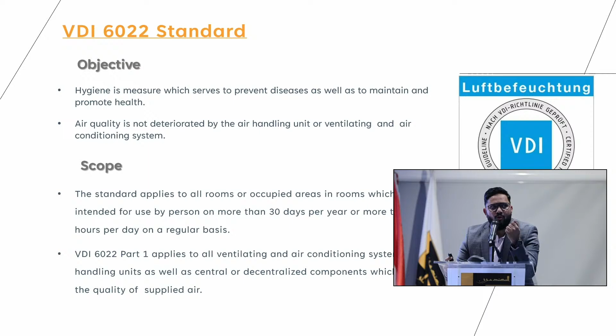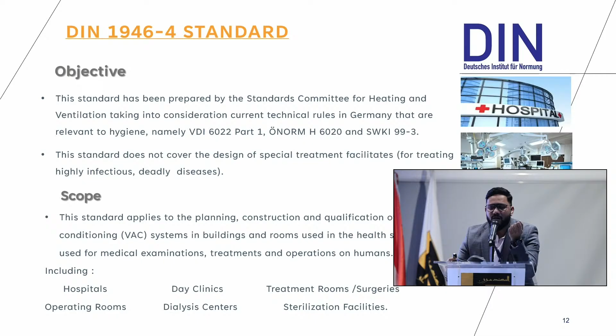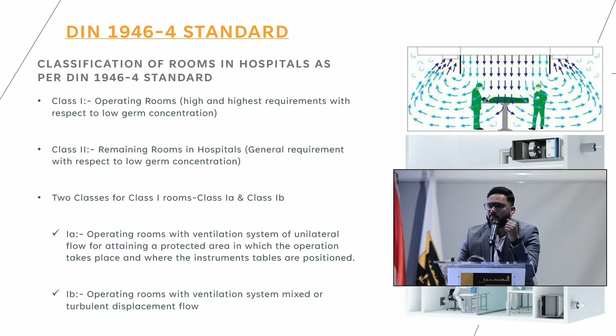To go with that, the other standard in hygiene applications is the DIN 1946, which is a combination of VDI 6022 and other German standards like ONORM H6020, where the scope is more into building rooms of critical applications, such as hospitals, day clinics, sterilization facilities and all. The standard classifies hospitals into two classes, class 1 and class 2. Class 1 will be the operating room, where there is a high requirement of hygiene and low germ concentration. Further, class 1 is divided into 1A and 1B. 1A, as you can see in the picture, is where the doctor is performing the surgery on the patient. Class 1B is in the operation theater, but not directly in contact with the patient where the surgery is being performed.